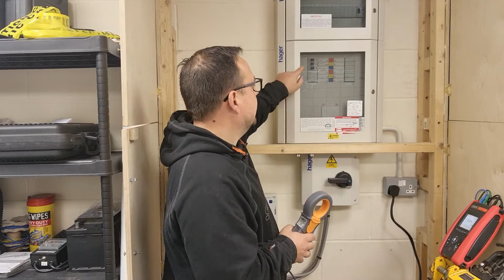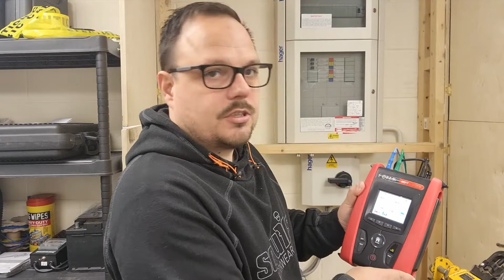It's a 32 amp radial circuit, and I've got the L2 conductor here, so we can get the clamp just around that. So if I pop that around there now, you can see I've got the socket circuit turned on. If I get as close as I can, I'll try and show you this on screen. The lighting's affecting it a little bit. If we go to power quality analysis, you can see there it's opened up that menu. Try and get it on camera if we can.